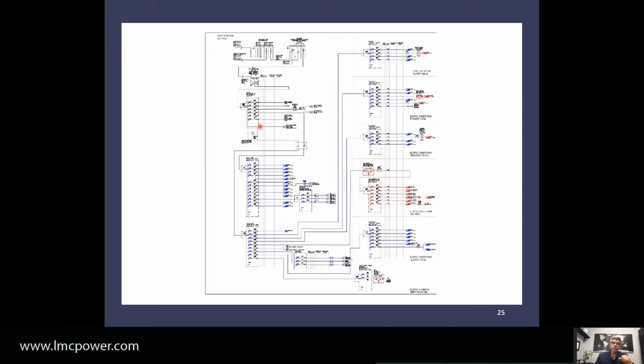It's not too complicated, so let's look at this one-line diagram. We have the input of the building going into the input surge panel. This input panel would be category C - good, even though everyone's on mute, I heard that. Category C, perfect. So we recommended about a 250 to 300 kA surge protector at the input of this building because it had a lot of branches. They also had smaller buildings where we just recommended 150 kA. This one was a little larger, so 300 kA at the input.